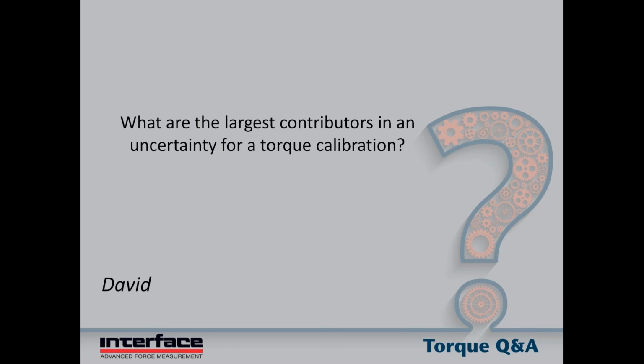We see that a lot with test machines, where the test machine is a torsion test machine that's applying a true torsion to a specimen, but to calibrate it, instead of using the calibrated torque sensor and trusting that, the end user puts an arm and a weight into the system, and then they've got a giant amount of bending in the system. They basically calibrate everything using that method, then you pull that out, remove the bending, and then start doing your testing. And really you've basically calibrated the system to a different condition than it'll be used. So you get very significant amounts of error and uncertainty from those types of conditions.